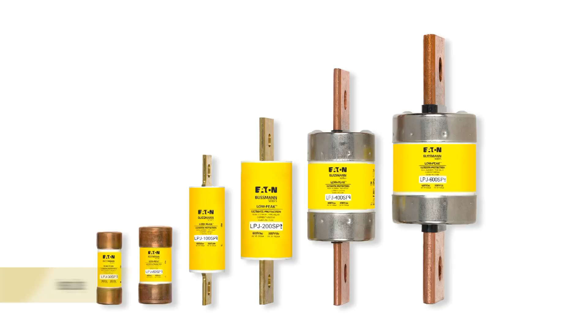Bussmann series Low-Peak LPJ fuses are rated at 600 volts and can be used on any system 600 volts or less, whether it's solidly grounded, ungrounded, impedance grounded, or corner grounded delta. A straight rated fuse or circuit breaker can be used to protect single-phase line to neutral loads when supplied from a three-phase, solidly grounded circuit.